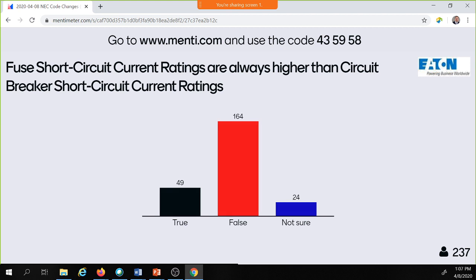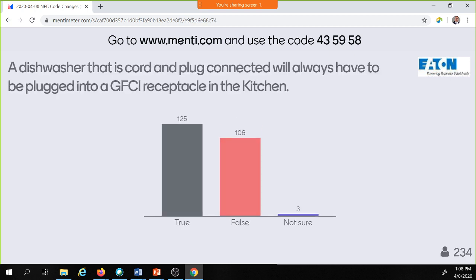Fuse short circuit current ratings are always higher than circuit breaker short circuit current ratings. 164 said false, 50 said true. The key here is fuses and circuit breakers do not have short circuit current ratings. They have interrupting ratings. Fuses and circuit breakers stop the flow of current, they do not hold together. Now you can argue there's some withstand ratings on these big power breakers, but circuit breakers and fuses have interrupting ratings. You've got to tune in tomorrow for our circuit breaker basics.